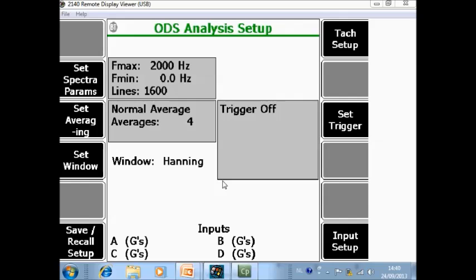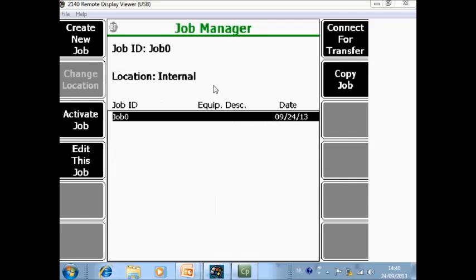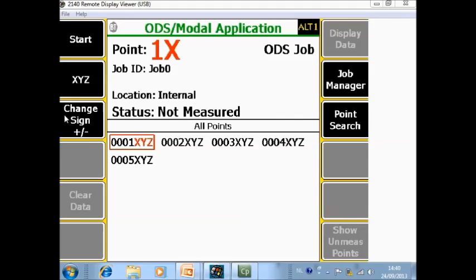With 4 averages, no trigger, and a Hanning window — that is OK for the setup. I accept it, and when you press enter once more you can finish the job definition and activate the job. We are now ready to collect data on those 5 points, but as explained earlier, we will show that in a separate video tutorial.